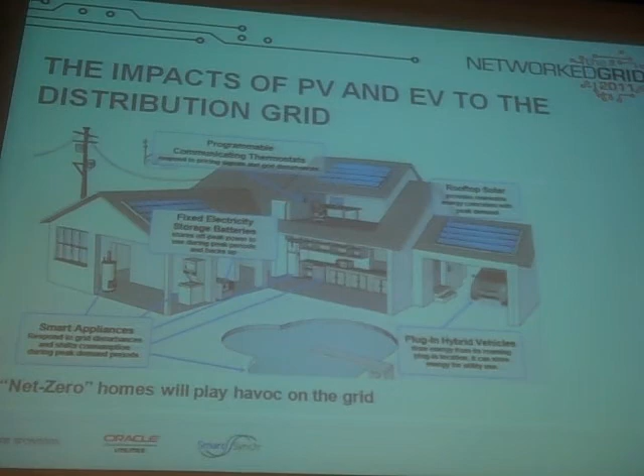In thinking about the impacts of solar and EV, the phases could become wildly imbalanced. Today, oftentimes what happens is that in the middle of the day in Southern California and other sunny spots, the voltage actually spikes above the 132 threshold, which forces the IEEE 1547 standard to kick in and trip off the solar panel so it stops producing energy.